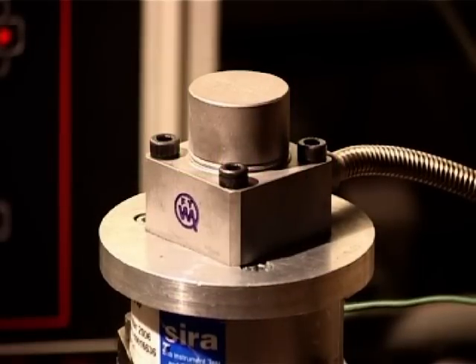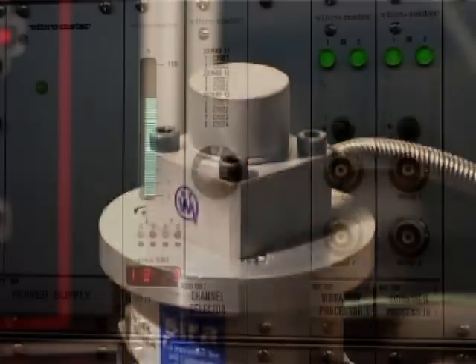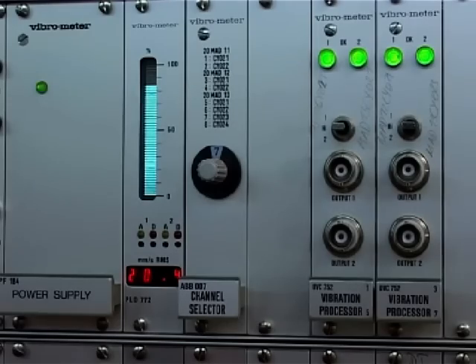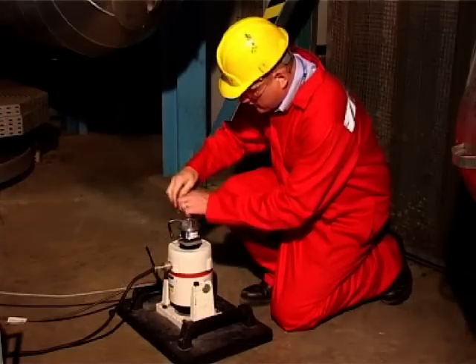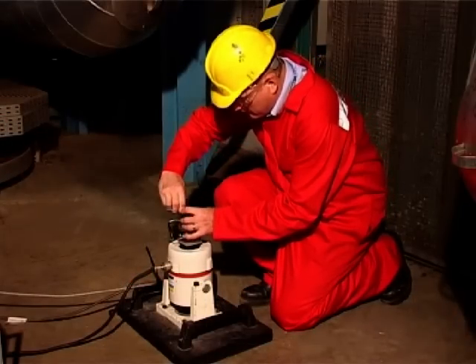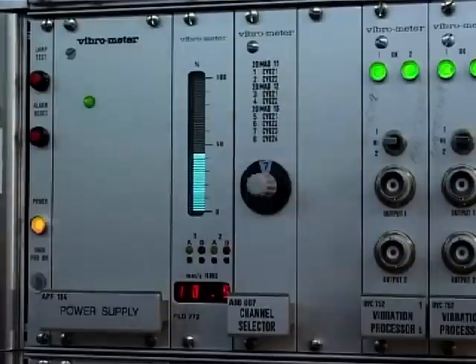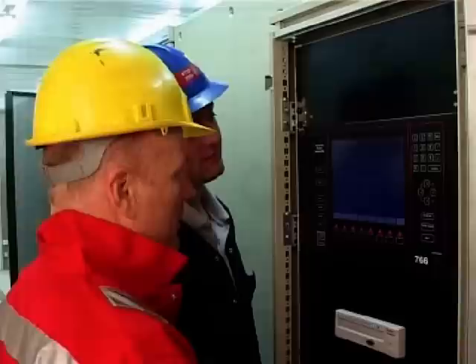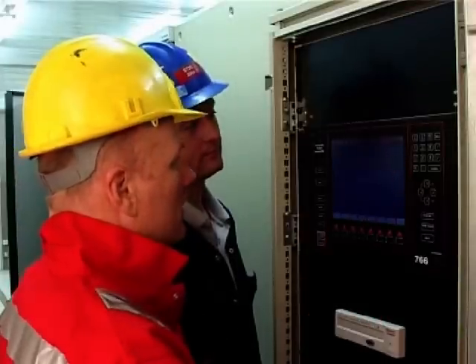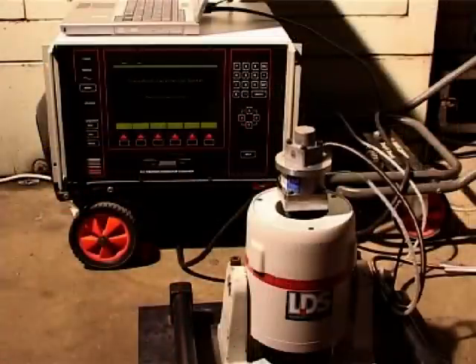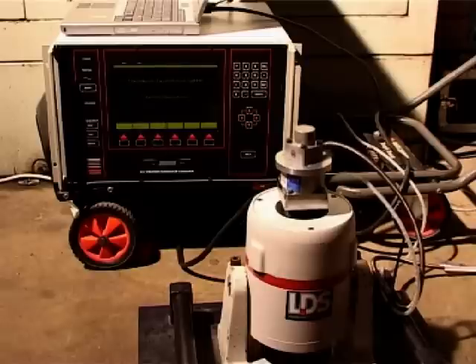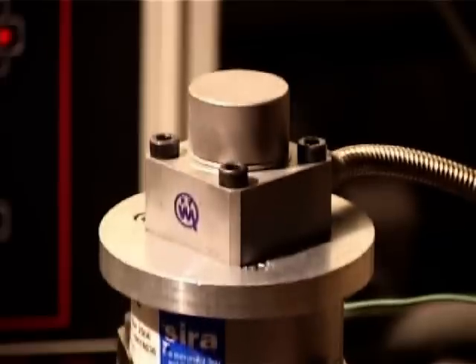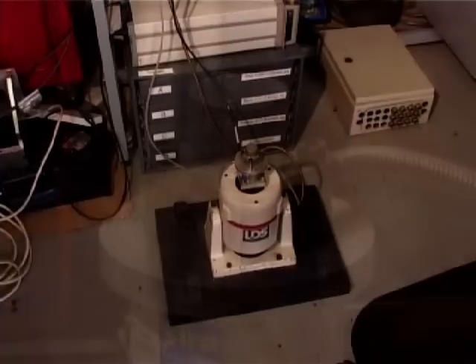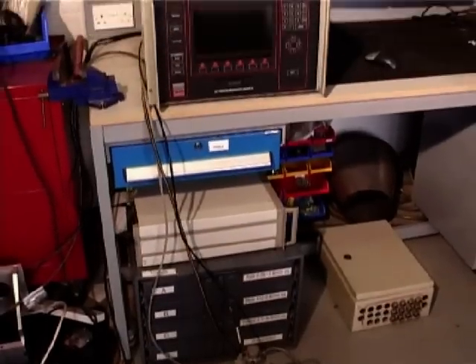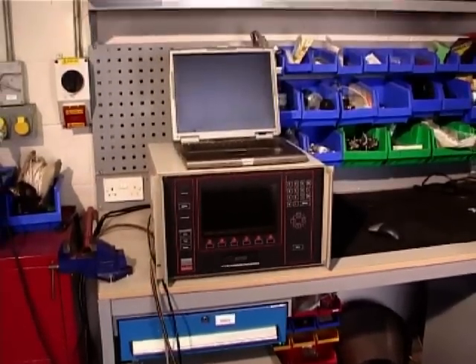With the TransCal, the vast majority of the calibration is achieved automatically. The only procedures that have to be performed manually are initially mounting the transducer and visually monitoring any analog display on the protection rack, condition monitoring system and control room consoles. Using the Beran TransCal ensures a high confidence when reaching decisions to extend the periods between maintenance or assisting maintenance personnel to pinpoint the cause of change in vibration.